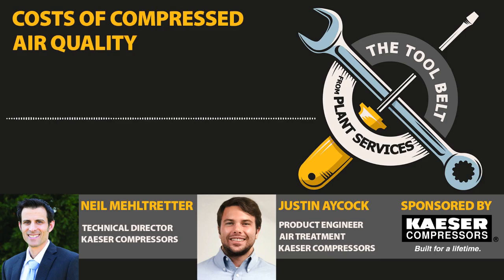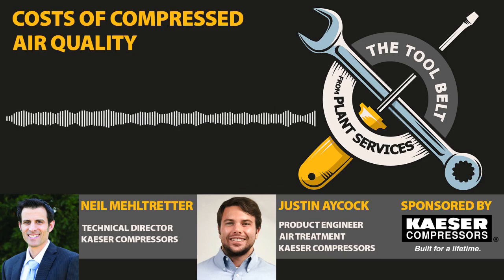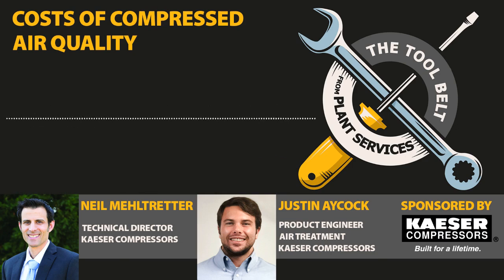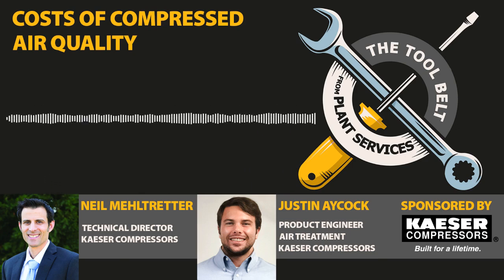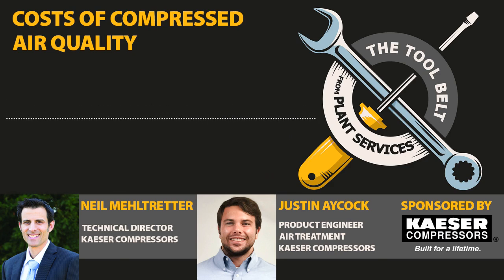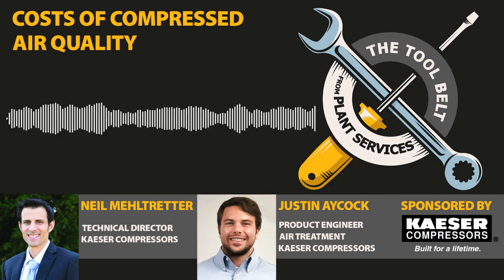So there's also an issue with oversizing dryers. If a dryer is oversized and you don't have any energy saving methods, you're missing out on opportunities to save a little bit of money. So for example, if you have a system that only needs 100 SCFM of air, but you have a dryer that's rated for 200 SCFM, after applying all the correction factors, and the dryer is non-cycling, then you're going to be using that dryer flat out. It's just going to keep running.